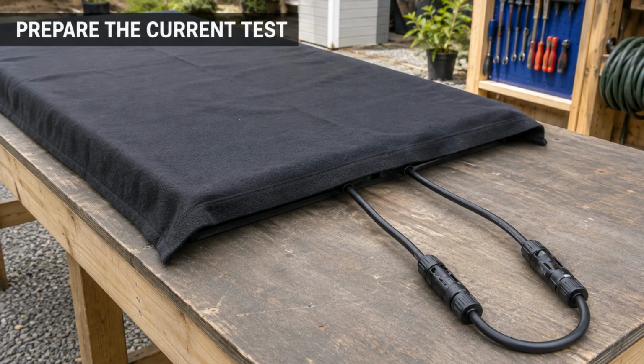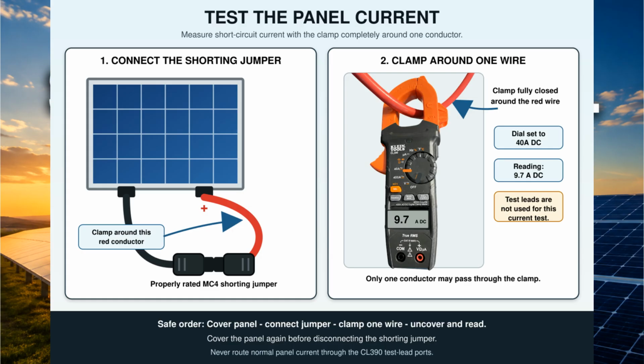Cover the panel before making the connection. Connect the positive and negative panel leads with a properly rated MC4 shorting jumper. Do not use loose meter probes to short the panel. Do not perform this beginner test on a series-connected array. Set the CL390 to 40 amps and select DC amps. Zero the clamp meter if needed.